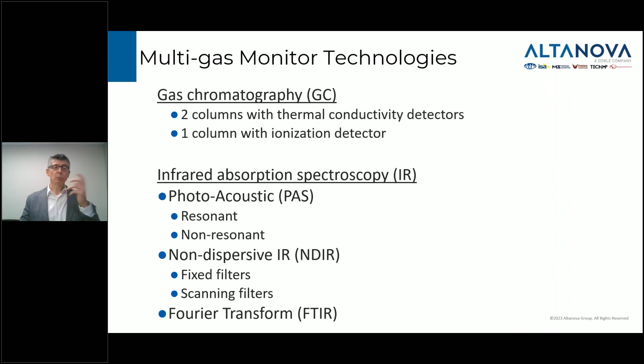The way I think about this is that there really are only two different ways of measuring the gases in this application. The first one is gas chromatography, which has been used by our labs for over 50 years. The other way is using some form of infrared absorption spectroscopy, where we take advantage of the fact that different gas species absorb infrared light at certain characteristic wavelengths. So it's really one or the other, and there are advantages to both types, with many different varieties of each. There are different types of GC monitors, different ways of doing the infrared absorption measurements, but ultimately every monitor falls into one of these two categories.